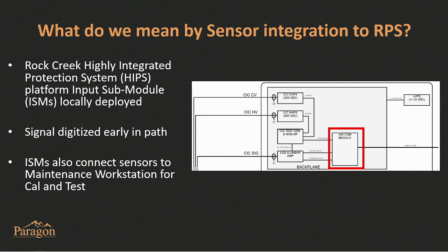So what are the benefits of that type of approach? You can apply this extension of reactor protection systems across most of the safety-related field sensors deployed today, whether that's a pressure measurement, a temperature measurement, or a movable in-core probe system. For all of those we can use the same methodology and move the reactor protection system boundary further out into the field environment. That gives us four different capabilities that I'll list here.